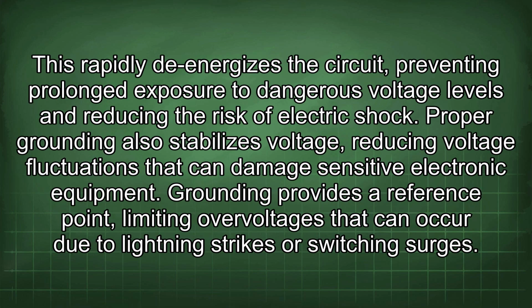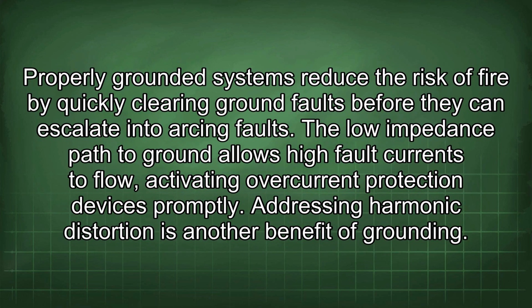This rapidly de-energizes the circuit, preventing prolonged exposure to dangerous voltage levels and reducing the risk of electric shock. Proper grounding also stabilizes voltage, reducing voltage fluctuations that can damage sensitive electronic equipment. Grounding provides a reference point, limiting overvoltages that can occur due to lightning strikes or switching surges. Properly grounded systems reduce the risk of fire by quickly clearing ground faults before they can escalate into arcing faults.